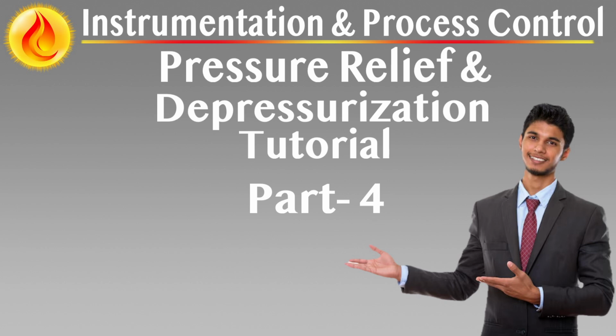Flare load dynamics and back pressure management. Flare header sizing is based not only on flow rate, but on pressure drop through the system. Dynamic analysis may be used to consider line packing during depressurization, temporary increase in pressure due to vapor accumulation, and header segment velocities, ensuring they stay below choked flow thresholds.